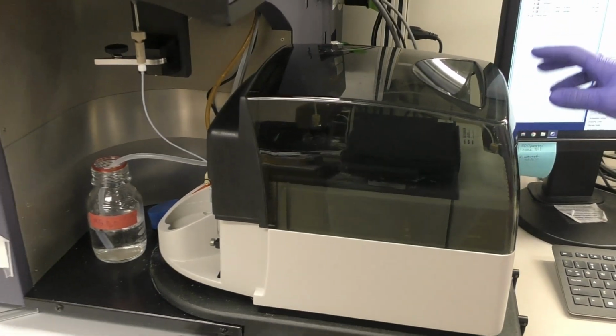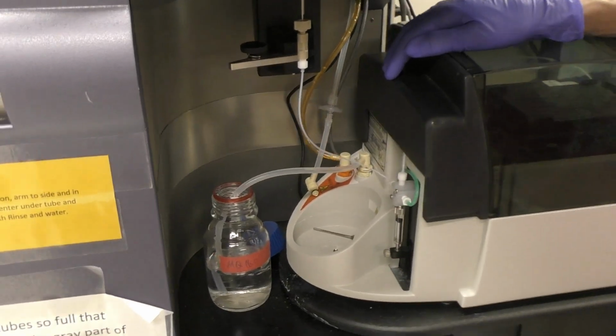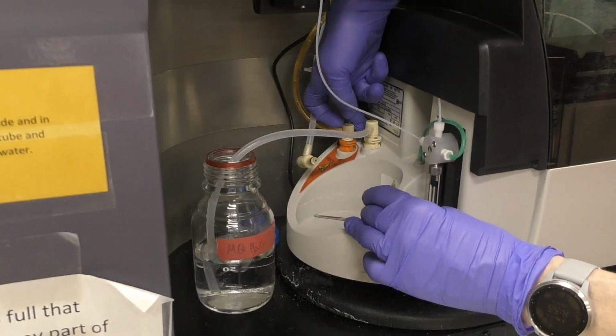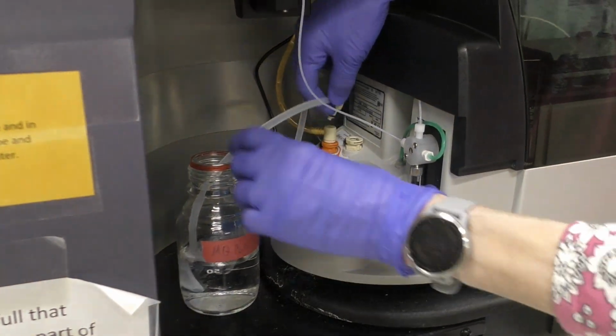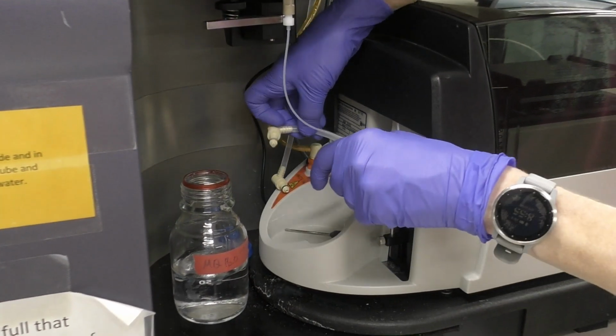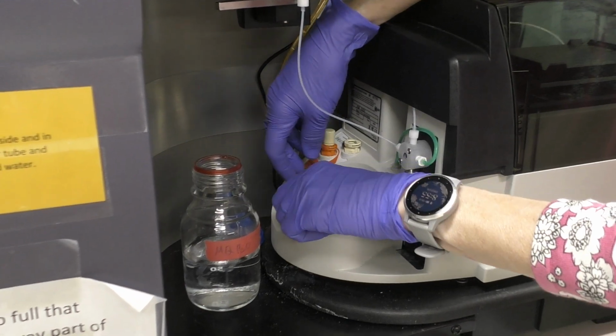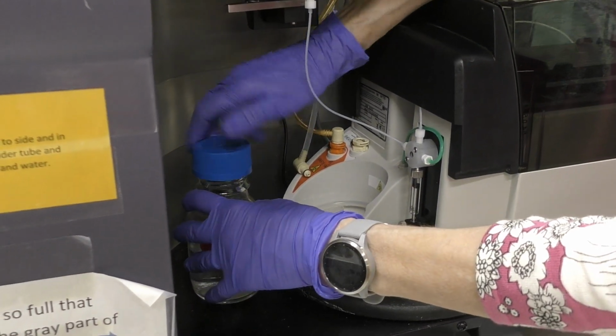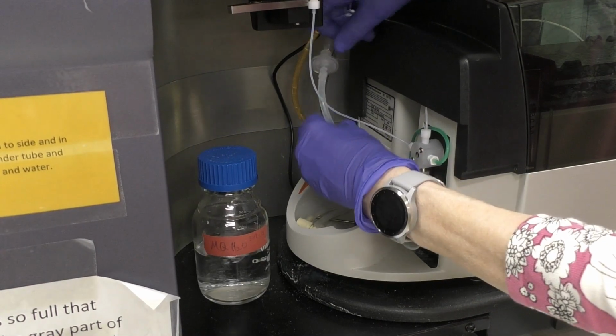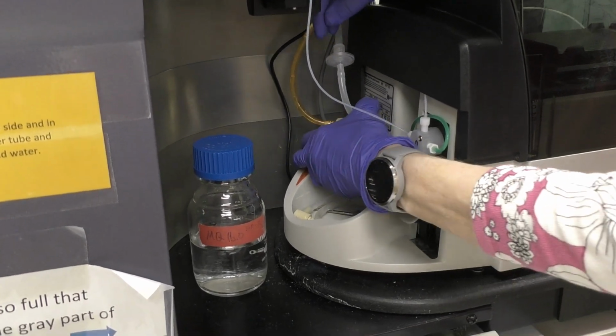Once you have primed 5 times with the DI water, which is an important step, it leaves the lines full of water instead of saline to avoid salt crystals buildup. Next, we want to remove this tubing by pushing the quick connect button, storing it here, replacing the sheath line into the quick connect.